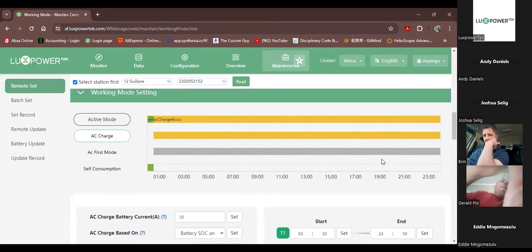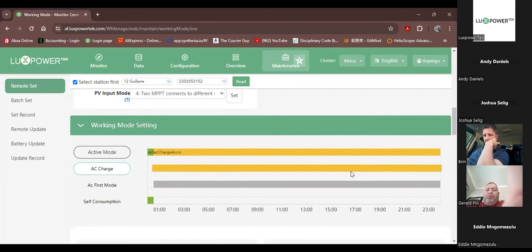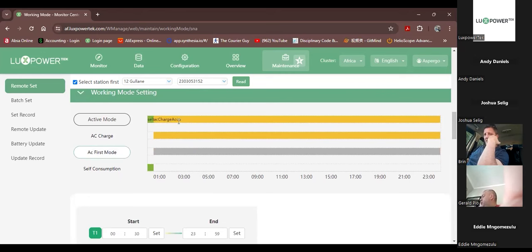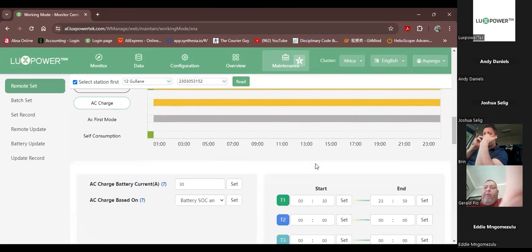Right, so here is the cool thing now, where we've got the working mode settings, and the nice thing here is you can actually see on the graph what the times are set. I can see that the AC first is set for these times here, and where I've got the green, that is where it's going to run in off-grid mode. On this particular site, we are using 15 minutes, I think it is, or half an hour, to run the system off battery, so that we can cycle the battery, because the site has got no PV whatsoever.